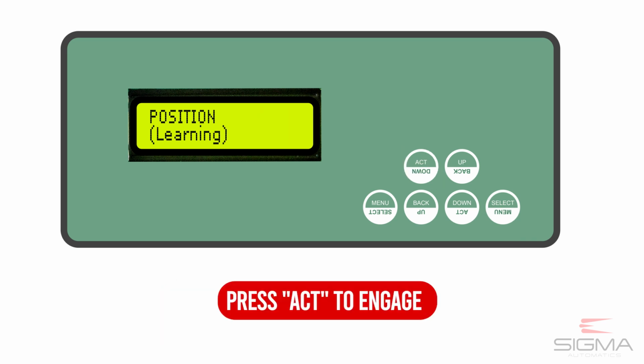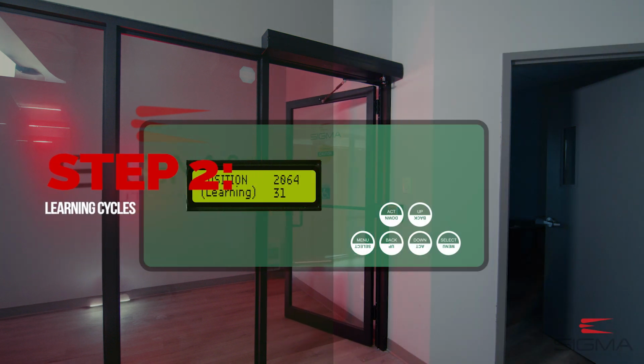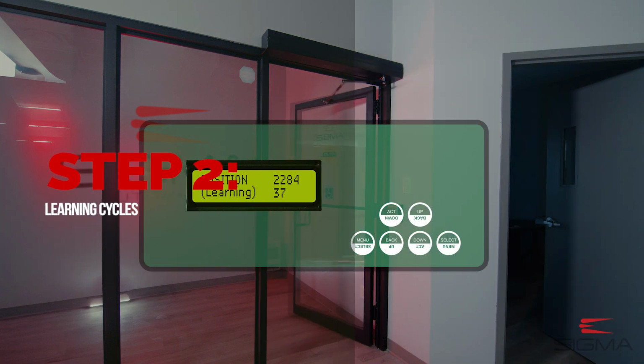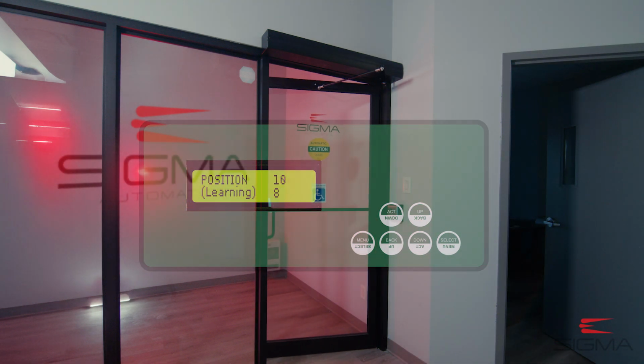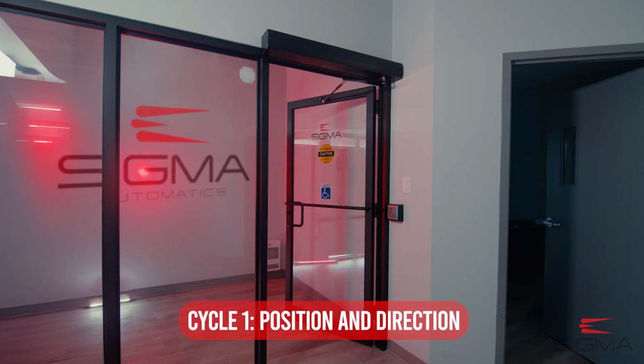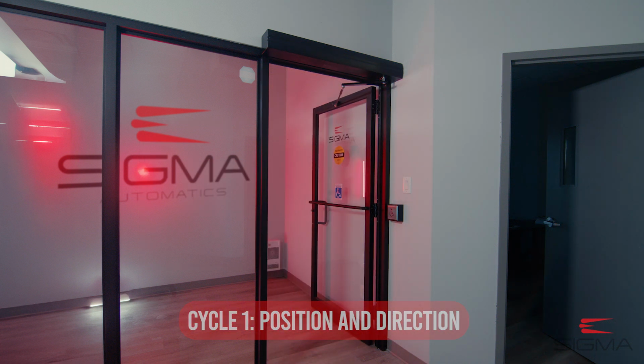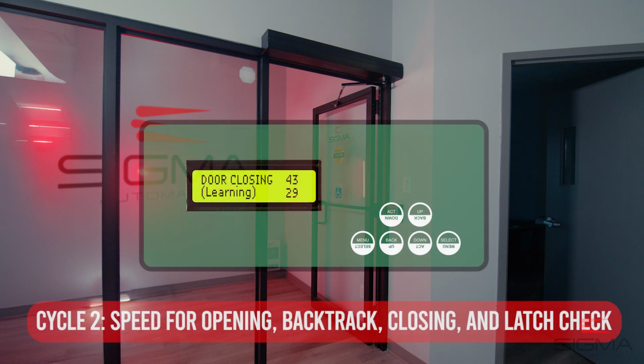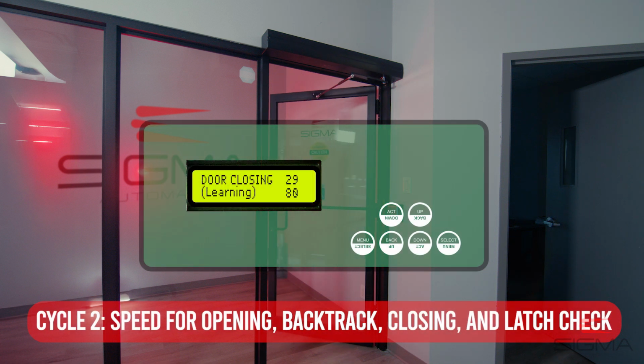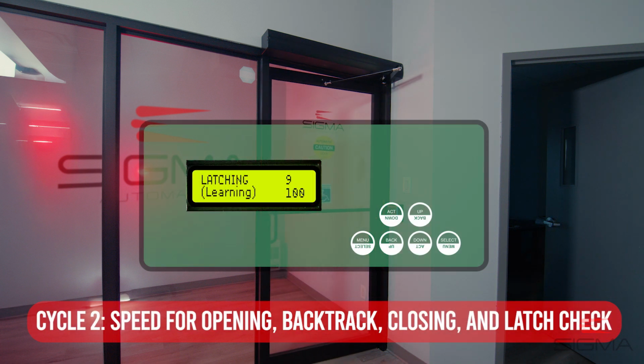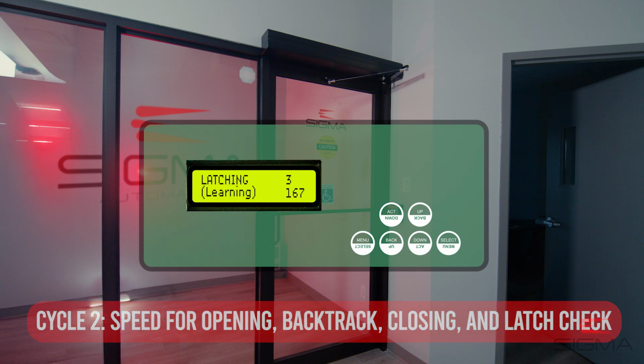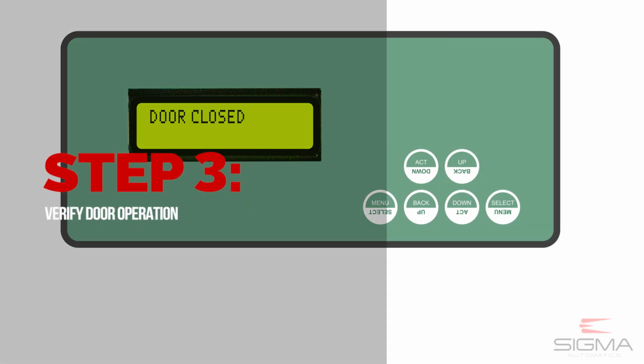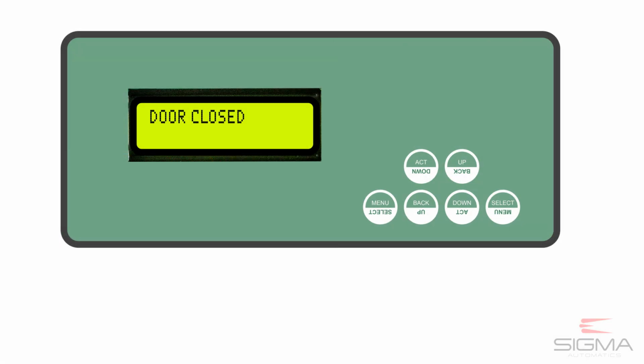The operator will now run 2 door cycles. The first cycle will determine the door's position and direction. During this phase, you might notice the door opening and closing a bit abruptly. That's normal. The second cycle will refine the door's performance, learning the door's opening speed, backtrack speed, closing speed, and latch check speed. Once both cycles are complete, the display will show door closed.